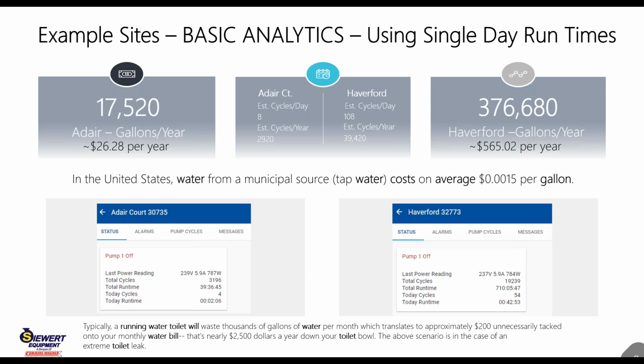Below, you see a couple of screenshots of this specific system's user interface. It gives power reads, volts, amps, and watts, total cycles since the system was installed, as well as today's information. Then there's access to a few other tabs that track alarm history, individual pump cycle data with timestamps, and messages, generally used by operators to note, for example, I was out at this home on this date and here's what I did. That way there's a running electronic record of service forever.